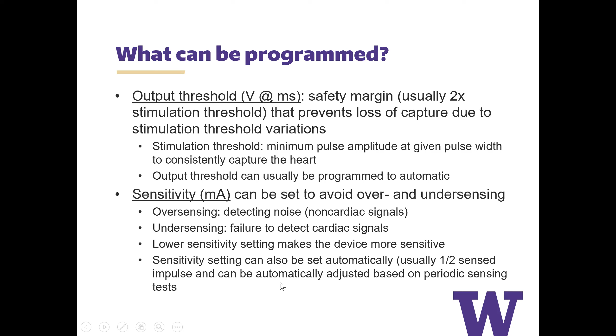Here's a point to keep in mind. When the sensitivity setting is lower, that actually makes the device more sensitive. It's not inherently intuitive when you initially think about it, but when you lower the sensitivity setting, the device is able to detect smaller signals, and so it becomes more sensitive. All of these things can nowadays be automatically programmed. The device is smart in the sense that output threshold can usually be programmed to automatic, and so can sensitivity. You usually want sensitivity set at half of the sensed impulse, and this can be automatically adjusted based on periodic sensing tests.